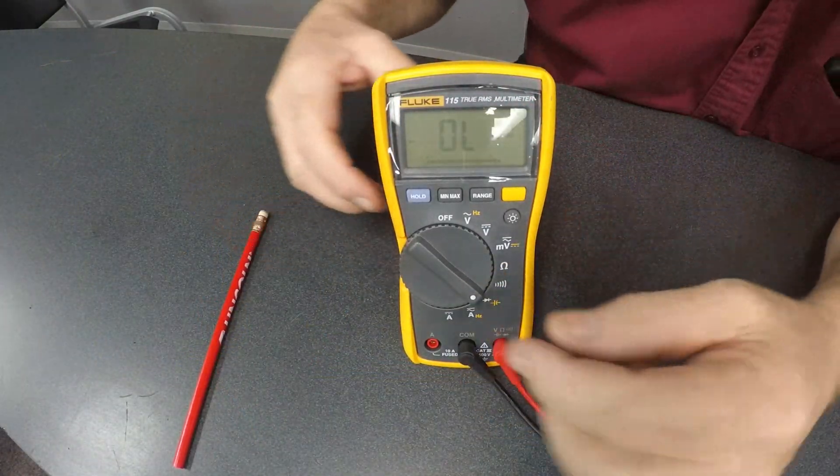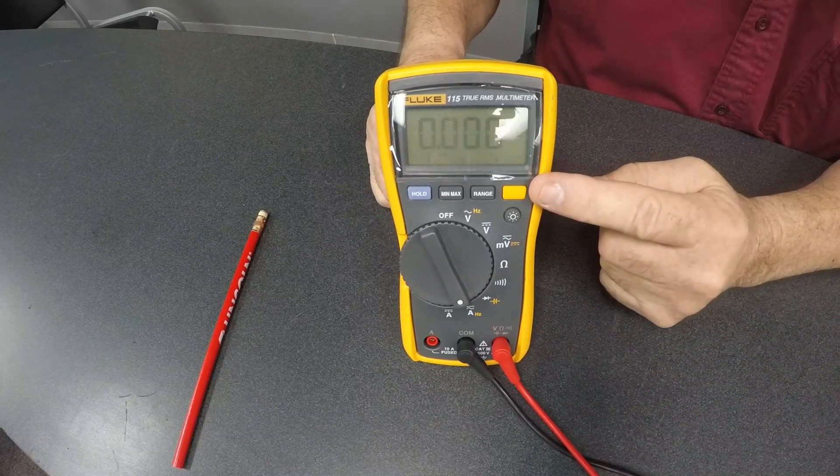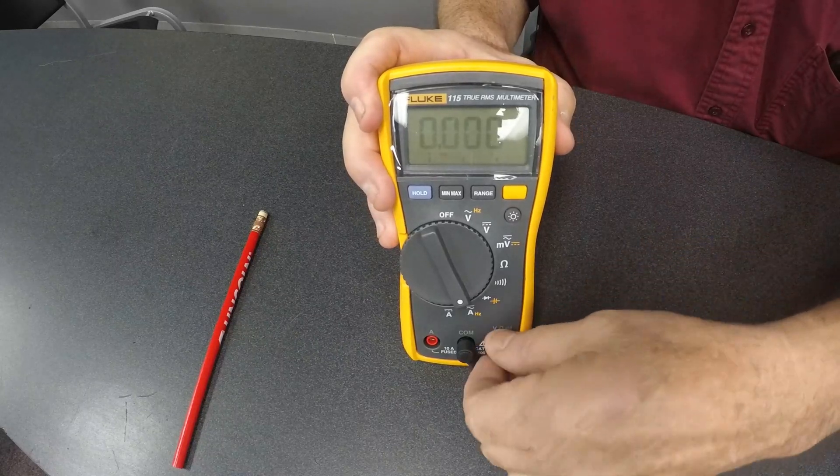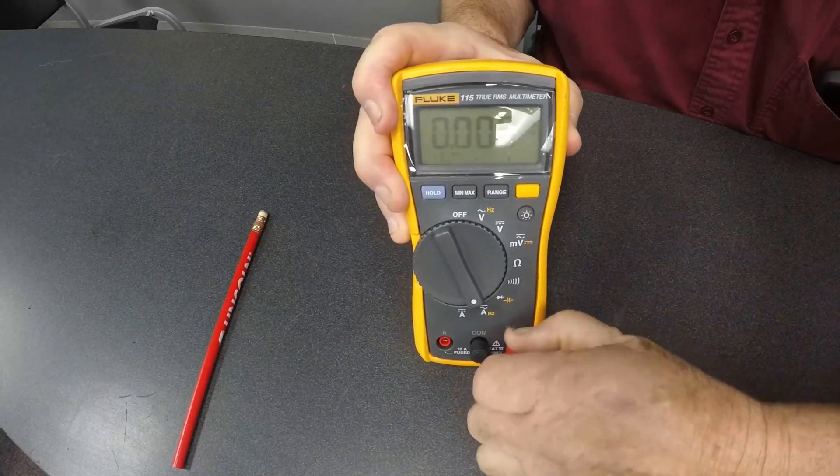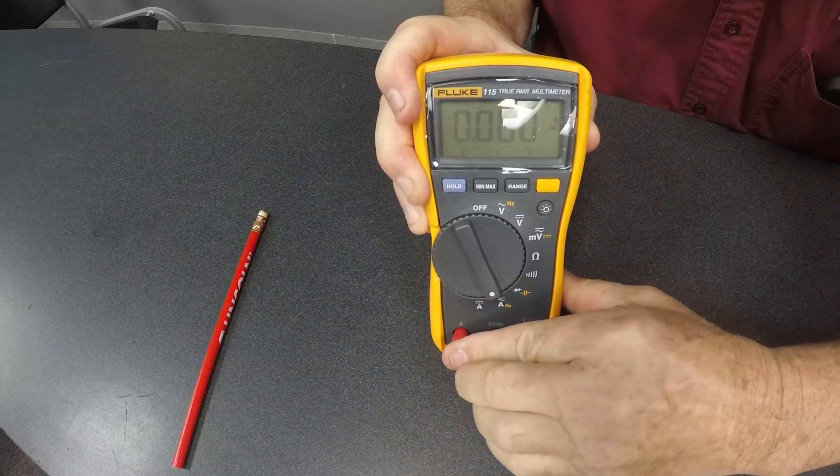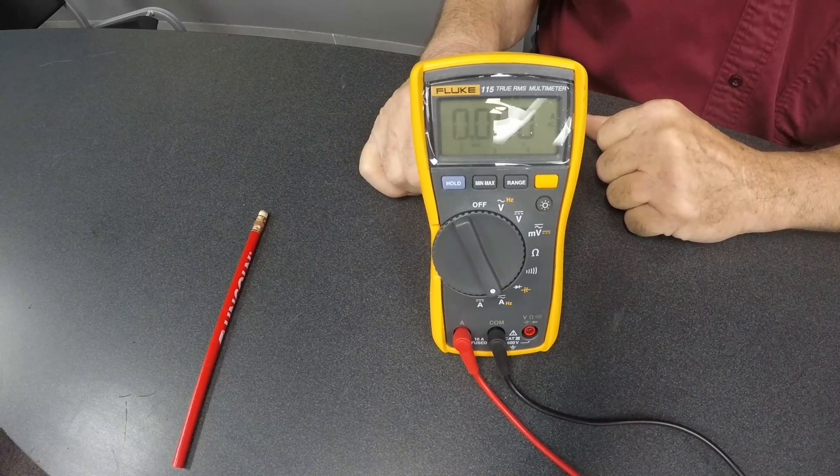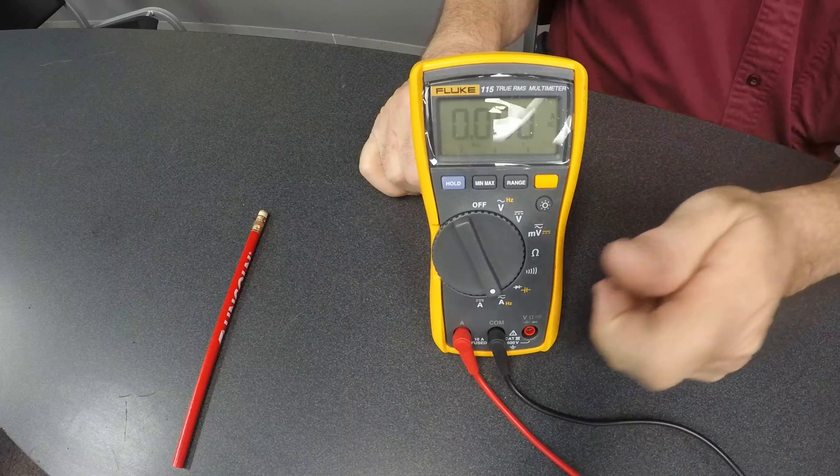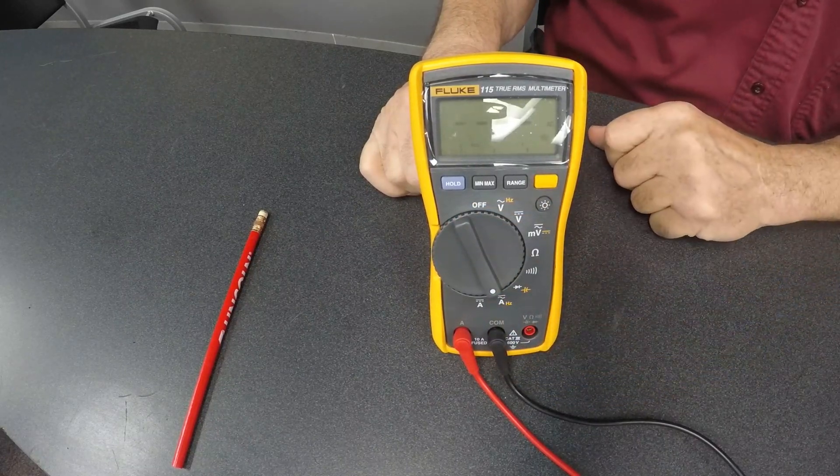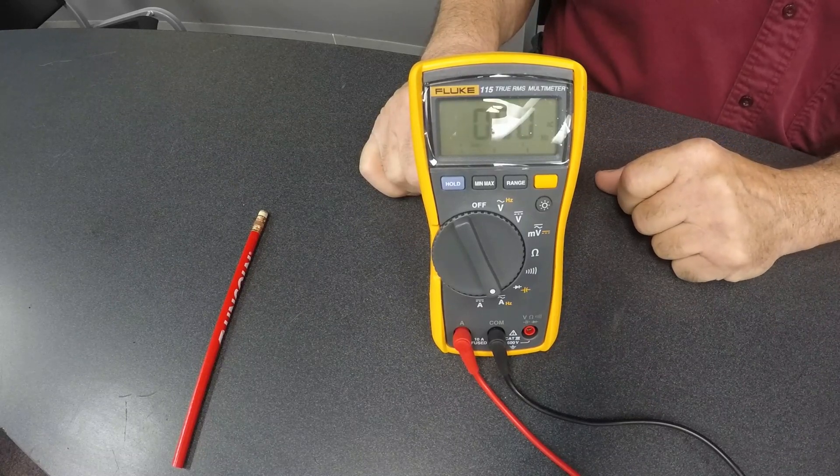The next one we're going to do is AC amperage. As you can see on here, it says lead. We have to take the lead out of the V-jack, which is for voltage. We take the red lead out of the V-jack, and we move it over to the A-jack for amperage. And we can test amperage. Remember, we test amperage in series, in line. Then the next one, then we hit the yellow button here, and we can check the hertz on amperage, how much is going on there.